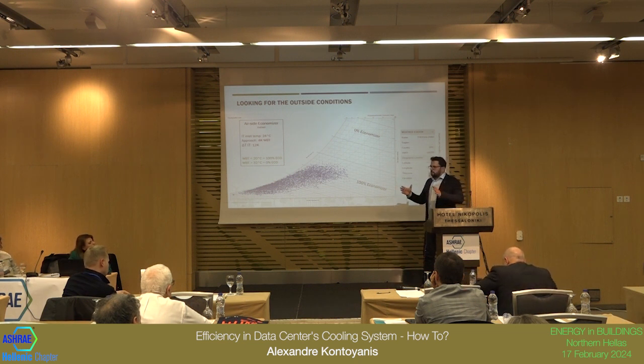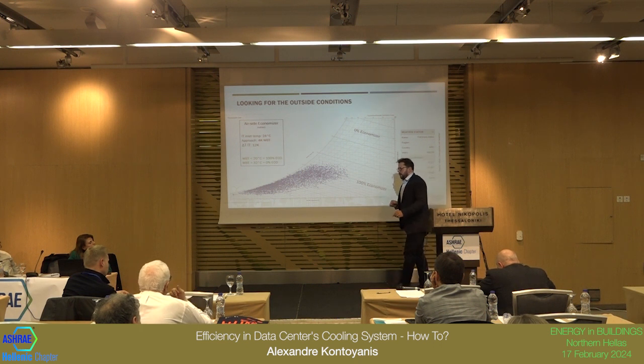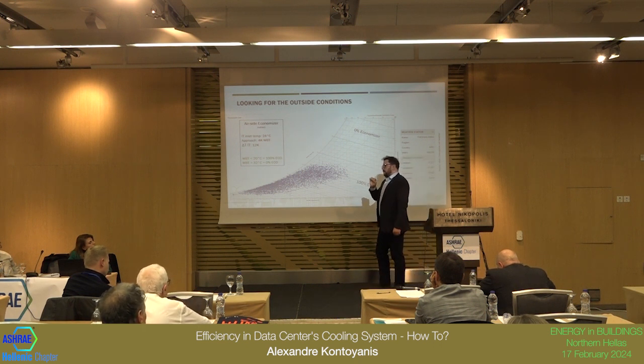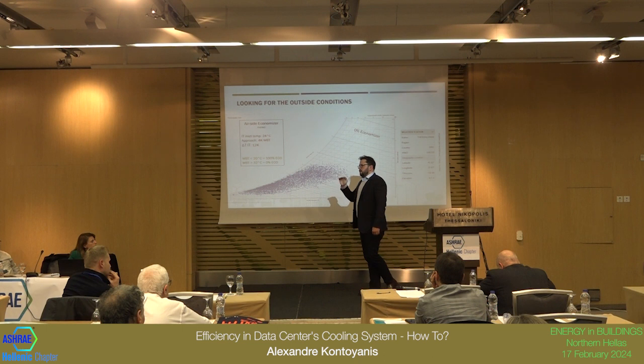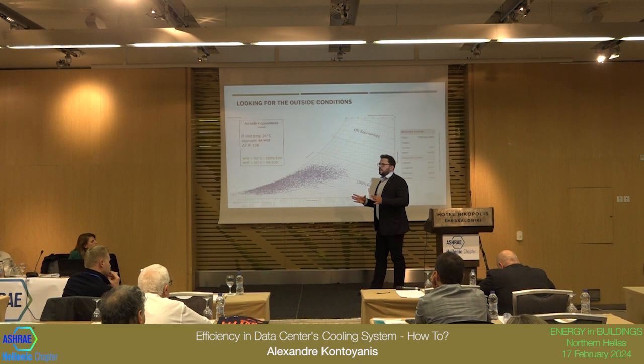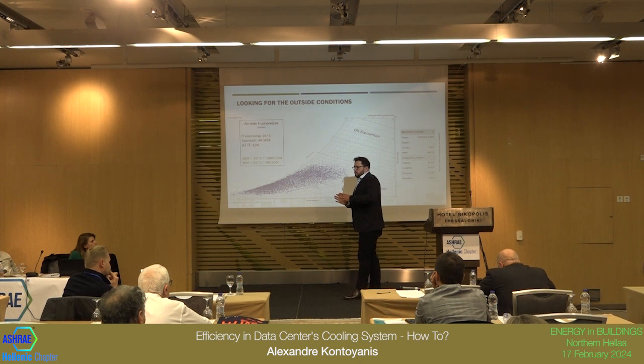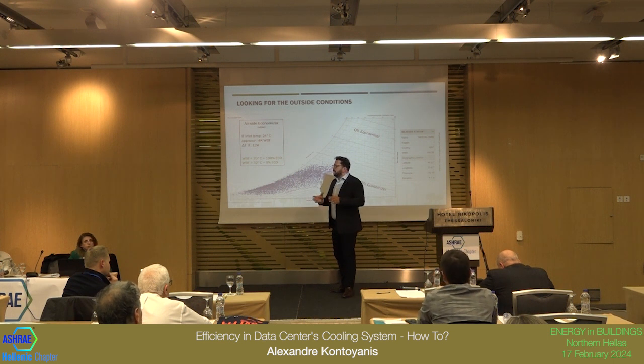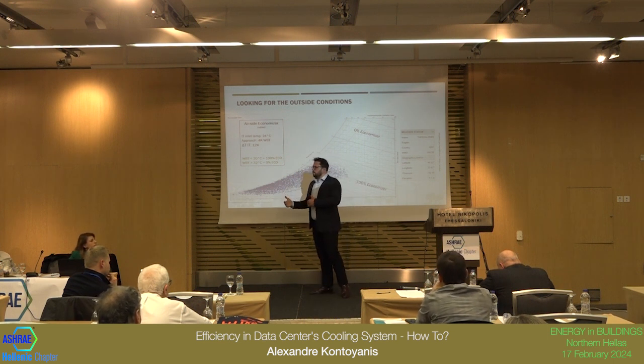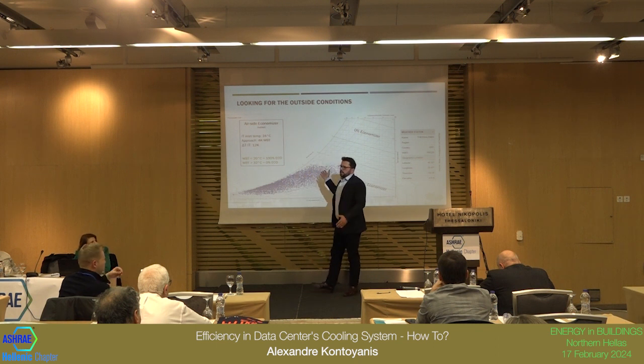And just quickly, it was just 5 minutes. We were discussing in Chicago, as the power rises from the chips, we are coming back to chillers, because even with liquid cooling, those applications will need lower temperature cooling. So if you're doing a data center for 10 years now, most consultants are advising you that maybe you don't need the chiller right now, but probably you will. So if you're building a 10-year data center, you should get ready for a new chiller, for example. Or you can install and use it partially.